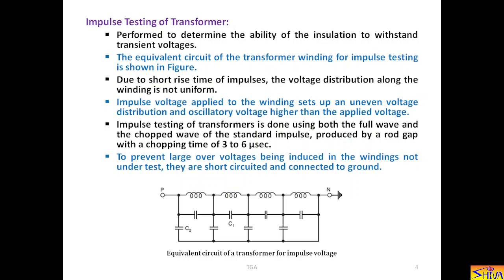I have already explained what is chopped impulse wave in the article on generation of high voltages. Now, here chopped wave testing is also important. Because when lightning overvoltage comes, then the lightning arrester chops down, lightning arrester discharges the lightning overvoltage. So, as a result, the residual voltage that is discharge voltage appears across the terminals of the transformer.